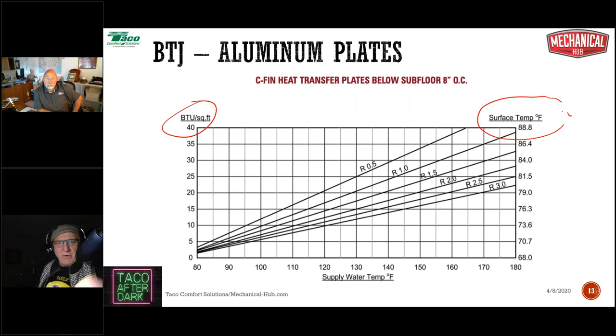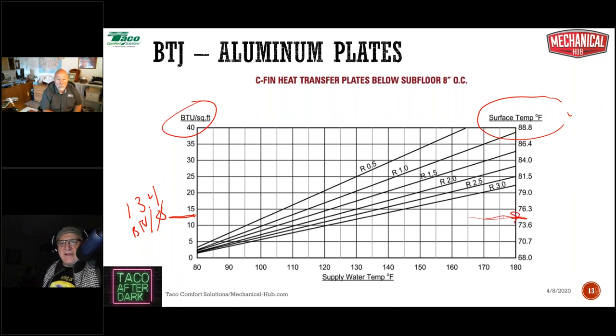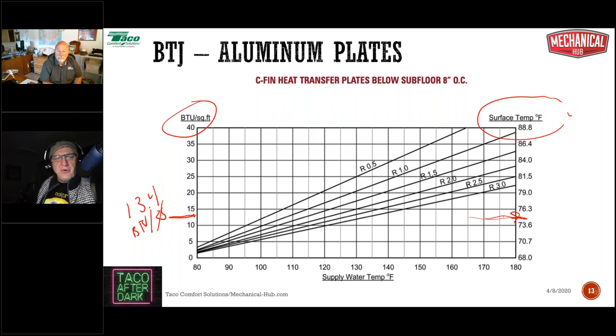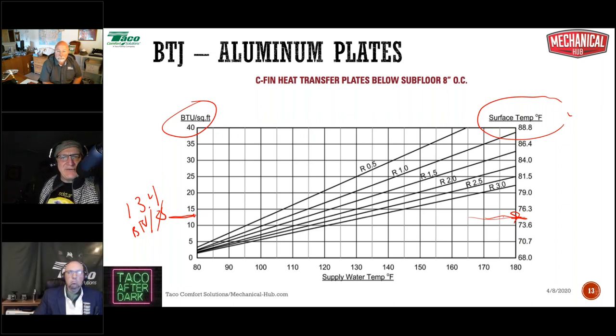Now, let's take a look. Let's forget what we have in the middle. Those lines represent finished floor R values. Our heat load is right about here, 13.4 BTUs per square foot. If we ran a line all the way over here, we would find the floor surface temperature that we would need to heat that room under design conditions. In this case, let's call it 75 degrees. So no matter what, I need a floor that's 75 degrees under design conditions to heat that room.